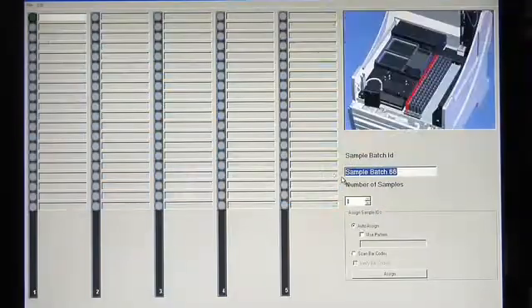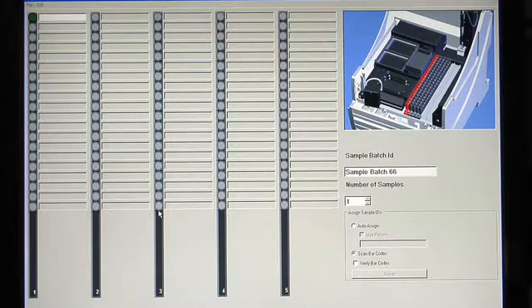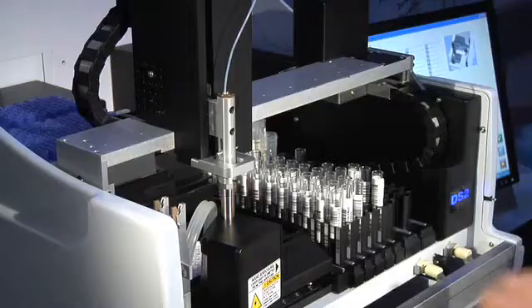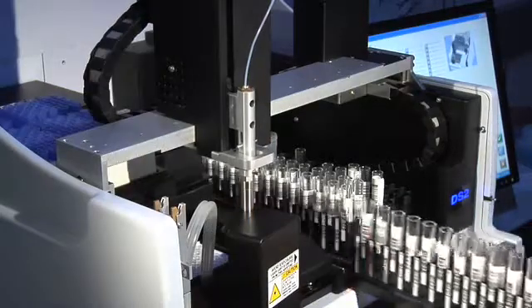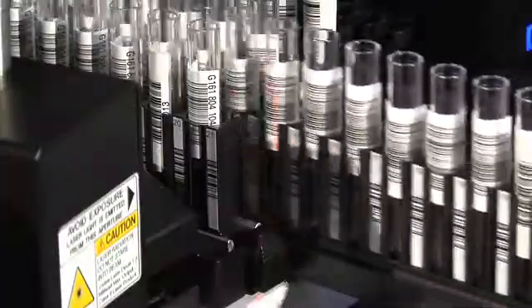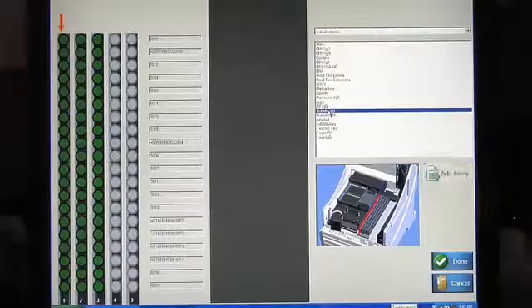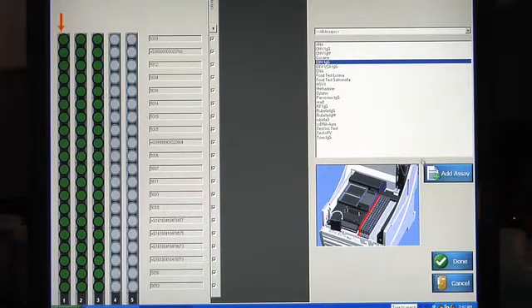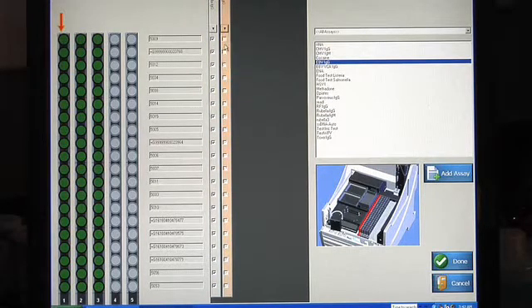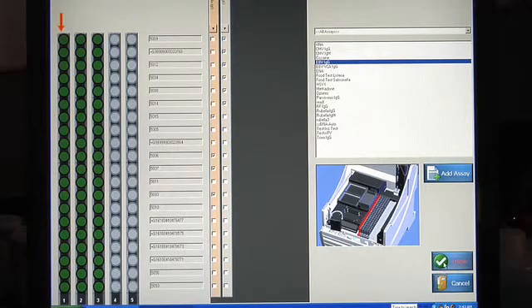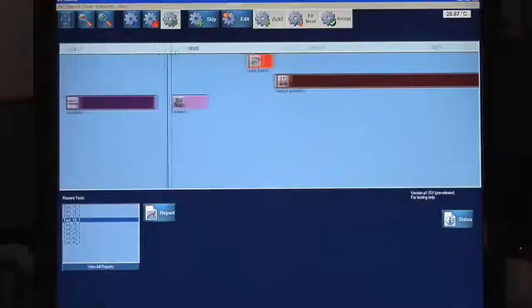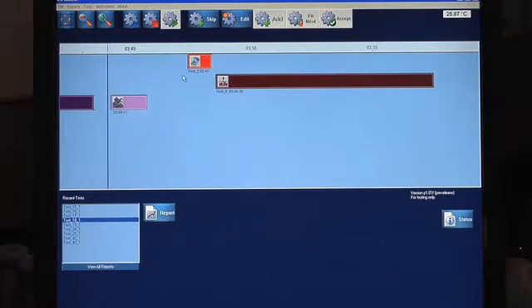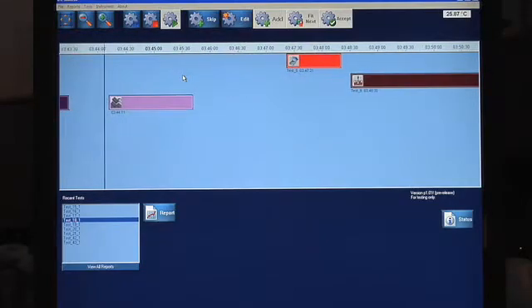For example, use the worklist editor to define your sample batch. 100 sample IDs can be scanned into the system in as few as 30 seconds with the optional barcode reader. Select one or multiple assays to run on specific samples. Hit done, and the DS2 schedules and presents a fully integrated timeline, showing all operations against a functional moving clock. You can see exactly how long your assay will take.